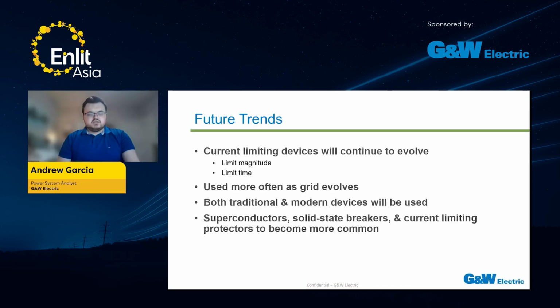Yep, conclusion. So what are some future trends? Current limiting devices are going to continue to evolve. These devices are going to focus on limiting the magnitude of the fault and the duration of the fault, because that's going to limit the amount of hazard and bring down that fault curve to a manageable level.